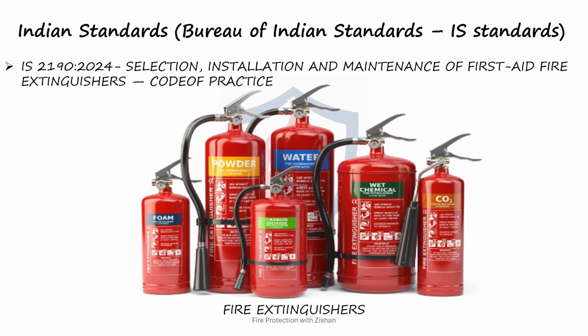Selecting the correct extinguisher is essential to ensure safe and effective firefighting. Water extinguishers are typically used for Class A fires involving ordinary combustible materials such as wood, paper, and cloth. Foam extinguishers are effective for Class A and Class B fires, especially those involving flammable liquids. Dry chemical powder, or DCP extinguishers, are versatile and can be used on Class A, B, and C fires. Carbon dioxide, or CO2 extinguishers, are primarily used for electrical fires and sensitive equipment because they leave no residue after discharge. Wet chemical extinguishers are specially designed for cooking oil and fat fires commonly found in commercial kitchens.